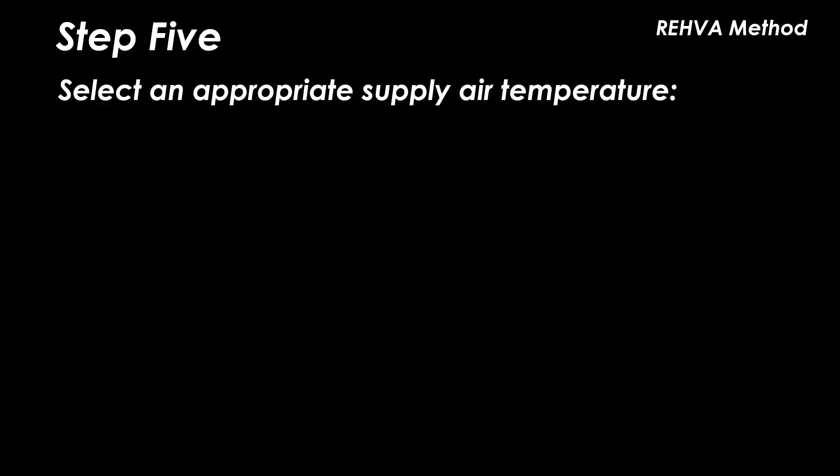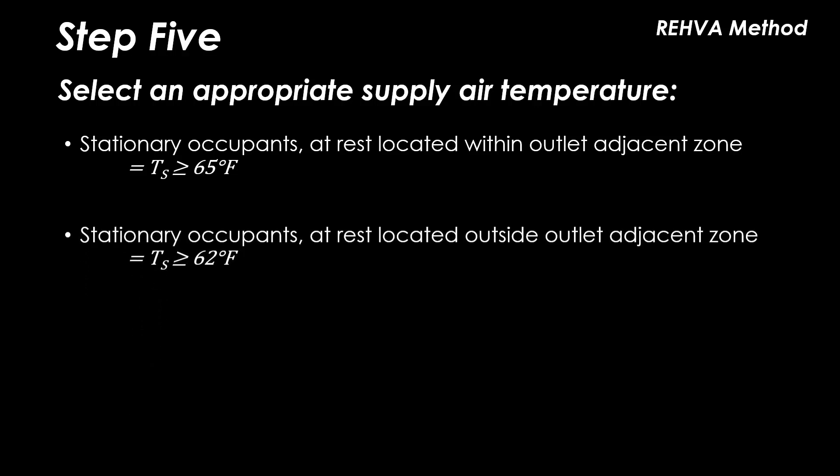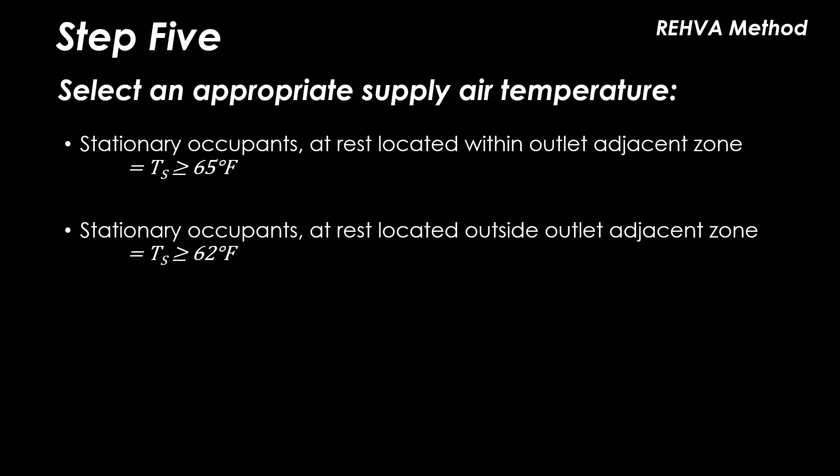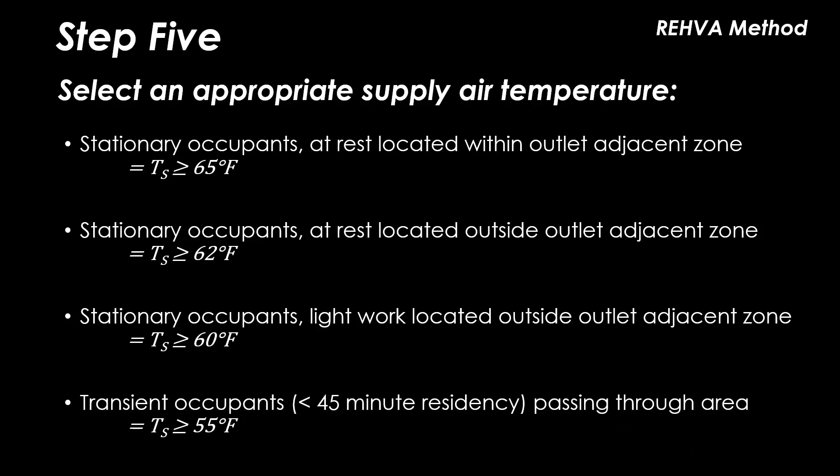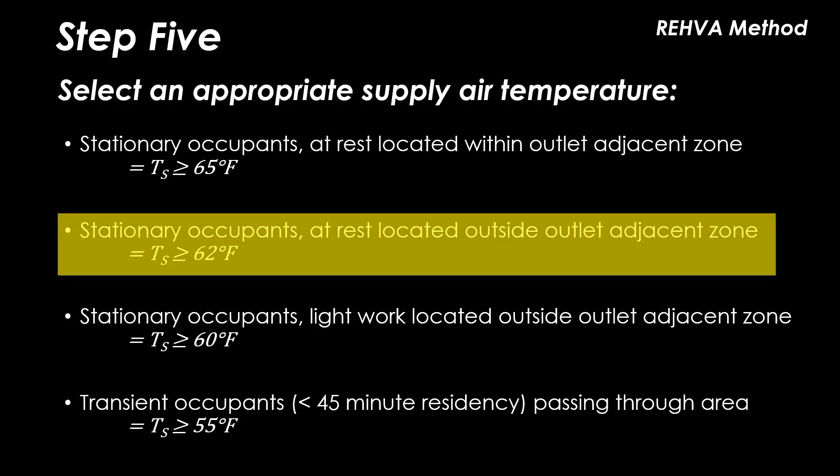In step five an appropriate supply air temperature TS is selected for the application for one of these four following scenarios. Stationary occupants at rest located within the supply outlet adjacent zone, TS should be equal to or greater than 65°F. Stationary occupants at rest located outside the supply outlet adjacent zone, TS should be equal to or greater than 62°F. Stationary occupants light work located outside the supply outlet adjacent zone, TS should be equal to or greater than 60°F. And for transient occupants passing through the area, TS can be equal to or greater than 55°F. A TS of 62°F has been chosen for our classroom example.